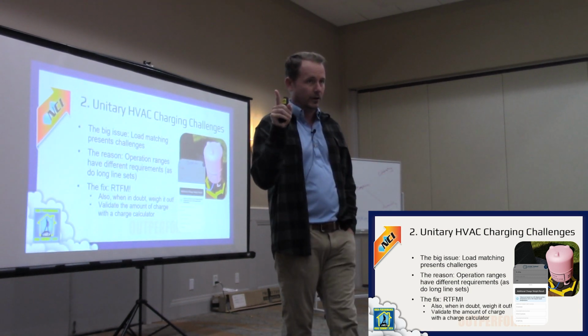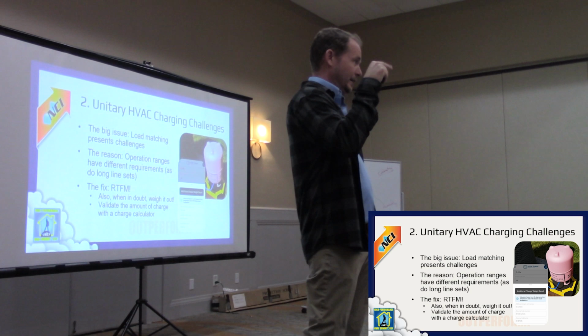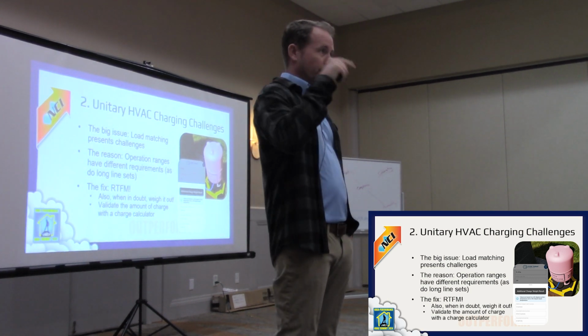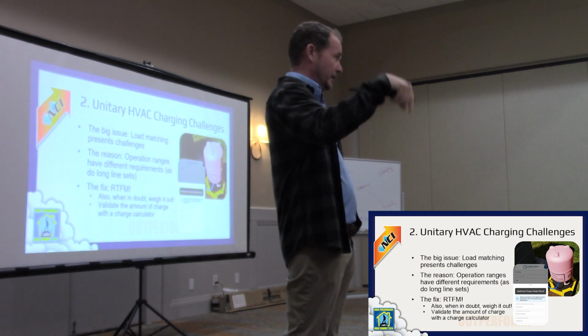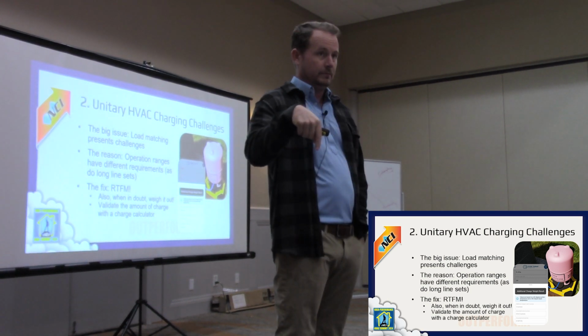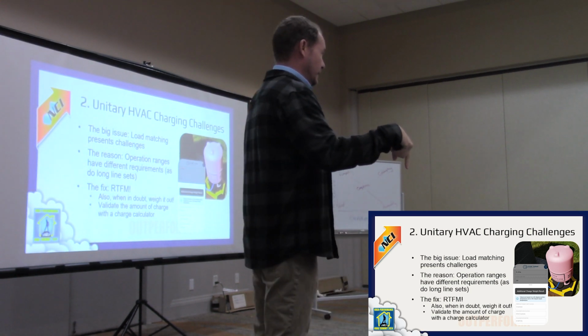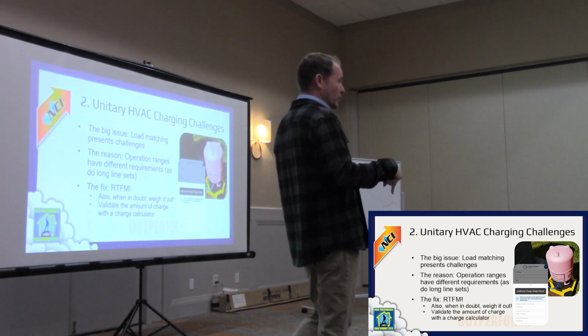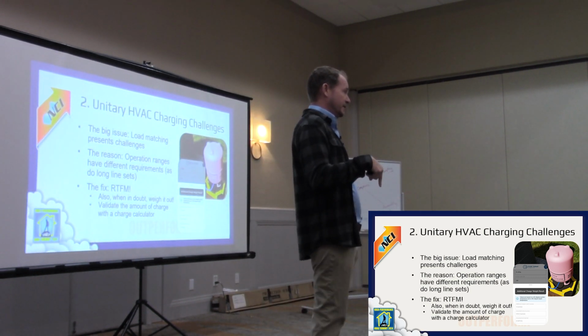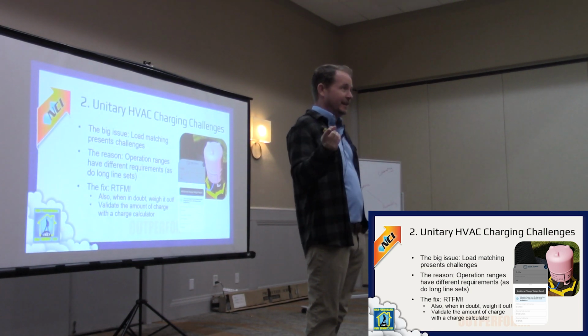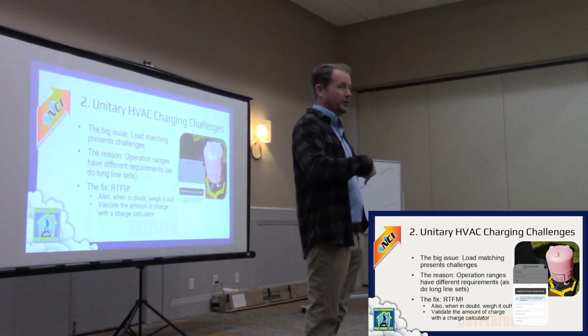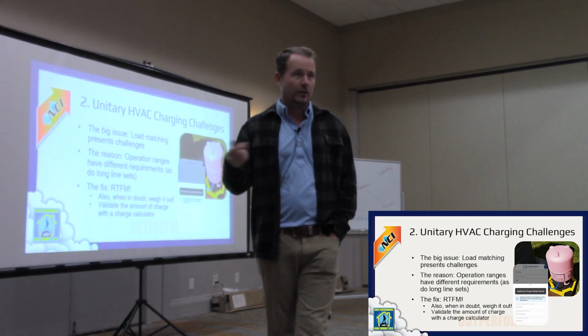Quick note I didn't mention last time - those recovery tanks given to you by a supplier are not clean. If you cut them open and look, there is almost certainly sludge down in the bottom of that recovery tank. They just empty it and put new refrigerant in it, back and forth - that's all that ever happens with that.